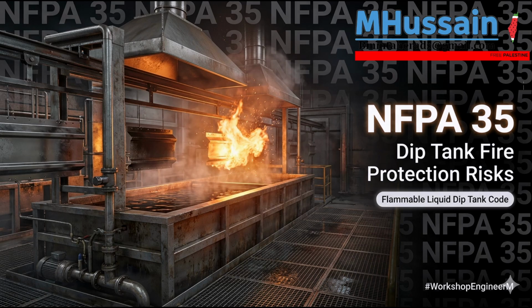That is terrifying. Furthermore, consider the thermal shock during a fire. If a fire breaks out, the piping gets extremely hot. Then, the fire department arrives and hits that red-hot cast iron valve with a high-pressure stream of incredibly cold water. Oh, the rapid temperature change causes the metal to contract violently. And because cast iron is brittle, that rapid thermal contraction causes it to crack and fail instantly. Which suddenly feeds an existing fire with a massive influx of fresh fuel. Exactly. Steel, being ductile, can absorb that thermal shock and maintain its structural integrity much longer. This is why the standard draws a hard, unforgiving line. No cast iron in flammable liquid service. It perfectly illustrates the gap between commercial plumbing and hazardous material engineering.